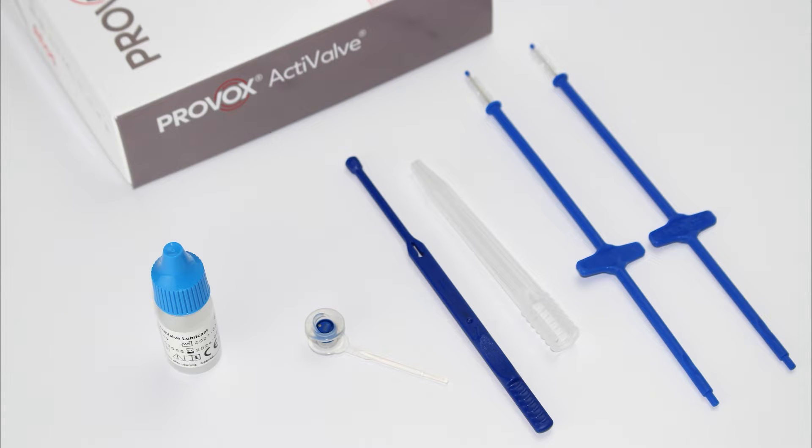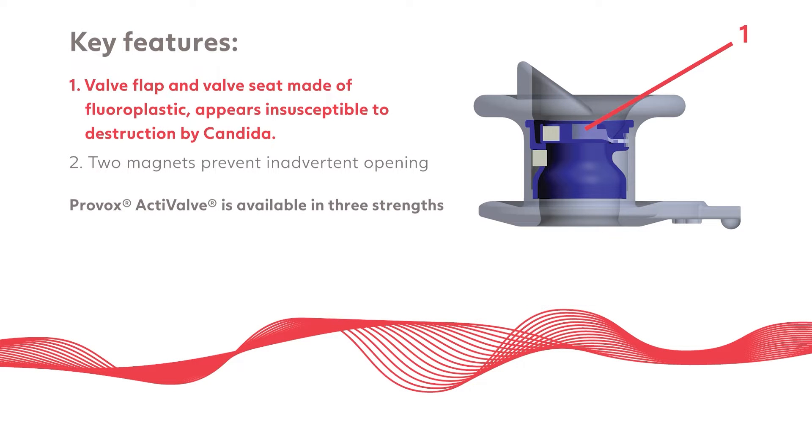Provox ActiValve is primarily designed for laryngectomy patients who experience early leakage through the voice prosthesis. The blue fluoroplastic material of the valve flap and valve seat help prevent the accumulation and infiltration of biofilm, which can disrupt the function of the valve and cause early leakage.